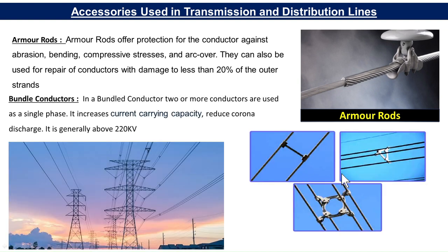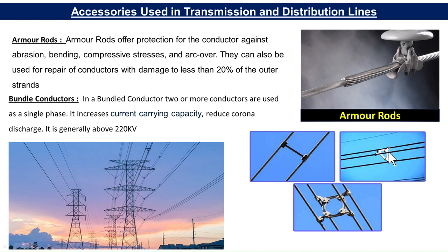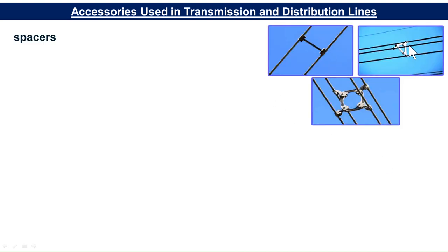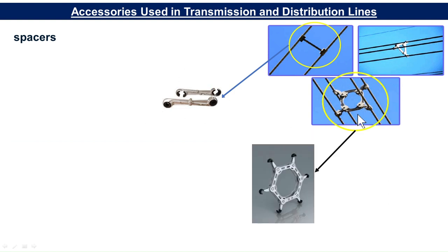Then there are bundled conductors. In a bundled conductor, two or more conductors are used as a single phase. It increases the current-carrying capacity and reduces corona discharge. Bundled conductors are generally used above 220 kV. As you can see from this transmission tower, three conductors are used as a single phase. The conductors are separated by a structure called spacers, which maintain the spacing between conductors in the bundle.